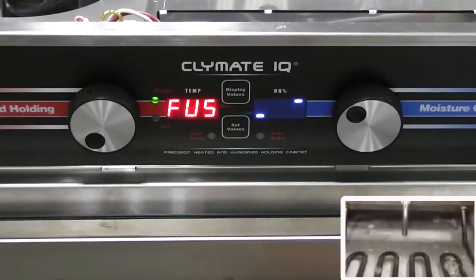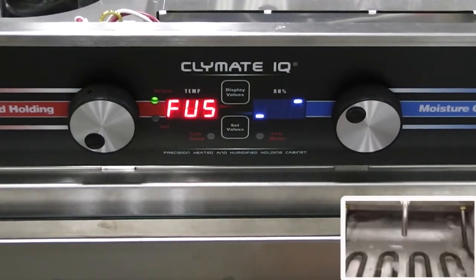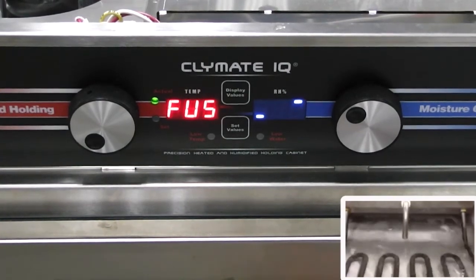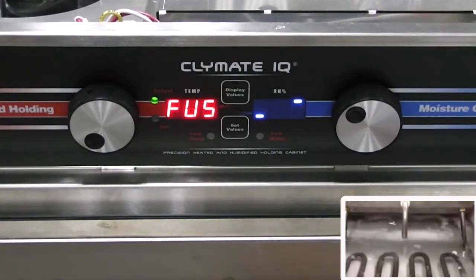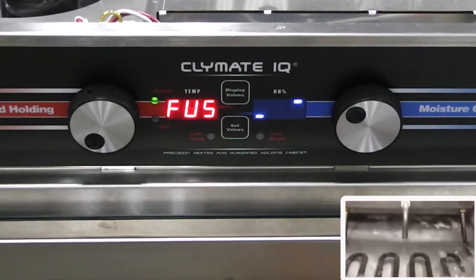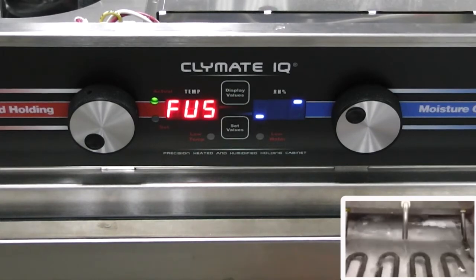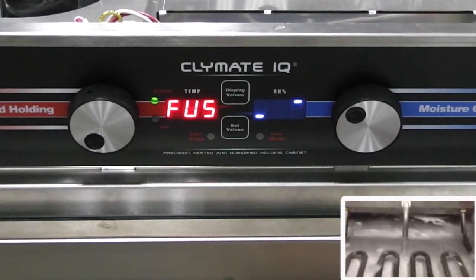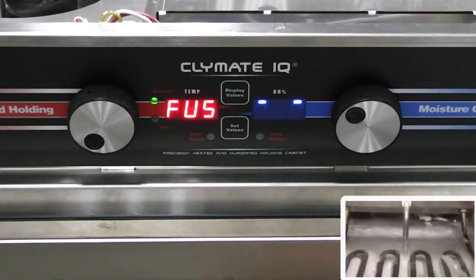Depending on the vintage of your unit, you could either have a float ball or a conductive probe. Since we're starting with no water in the pan, water is not touching the probe, so the left dash is down. As water fills, water touches the probe, the left dash goes up, making a chirp sound. The center dash will flash, as you notice, about every 3 to 5 seconds, indicating that there is power to the sensor. The dash on the right for older standard units is up or down indicator for units with the double float switch. Ours is always up due to the jumper between REF and high on the control board.